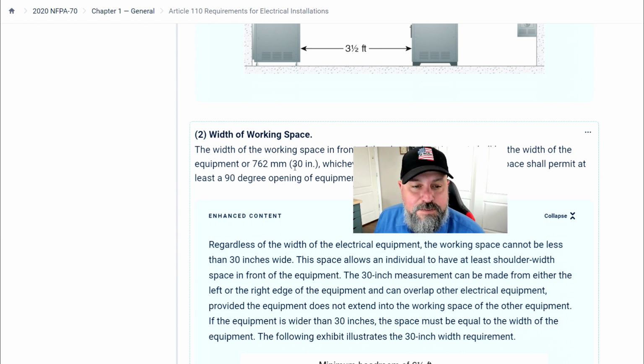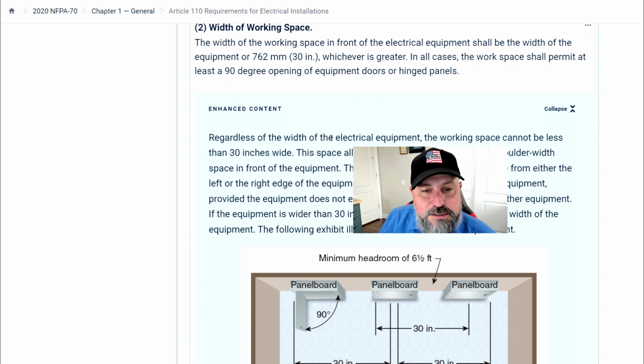Or if the equipment is actually larger than 30 inches, then the equipment space for that is whatever the width is of the equipment you're installing. Regardless of the width of the electrical equipment, the working space cannot be less than 30 inches wide. This space allows an individual to have at least shoulder width space in front of the equipment. The 30-inch measurement can be made from either the left or the right edge of the equipment and can overlap other electrical equipment, provided the equipment does not extend into the working space of the other equipment.